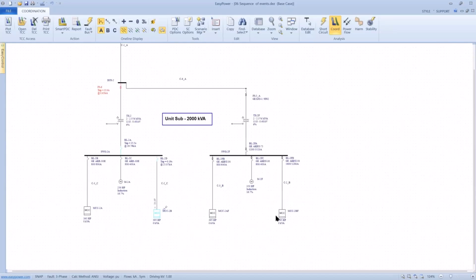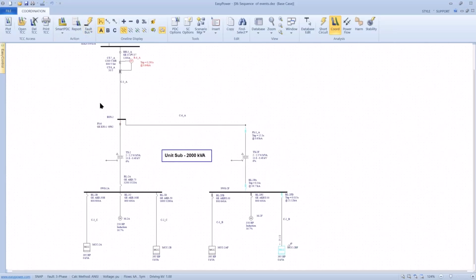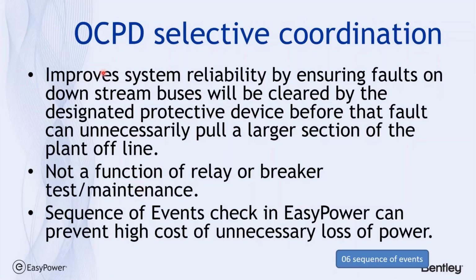Pick out another single load, fault it. We see we don't have the problem except with the relay. So that again is even if the client didn't ask for coordination, before you start making recommendations on incident energy protection, you may want to double check your coordination.